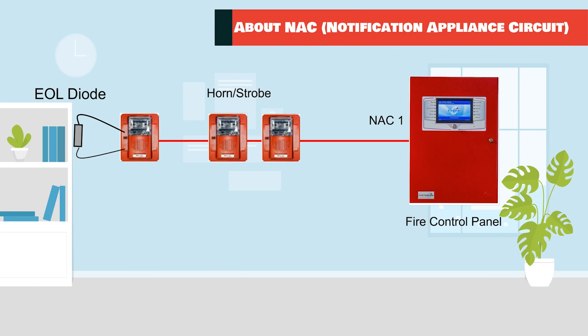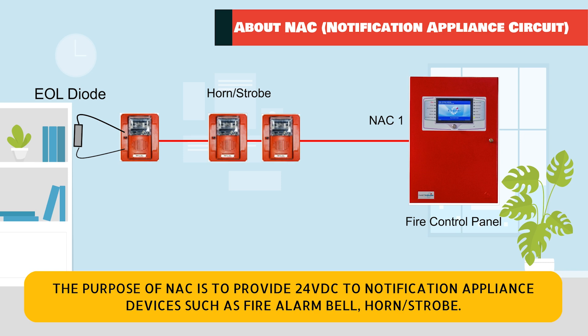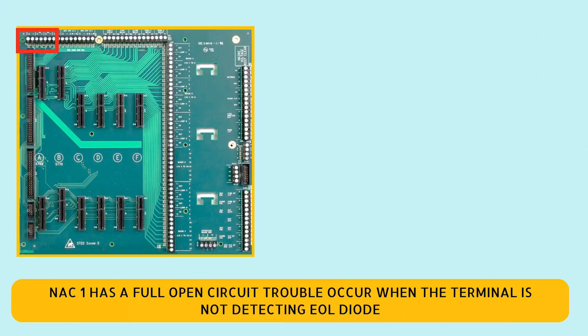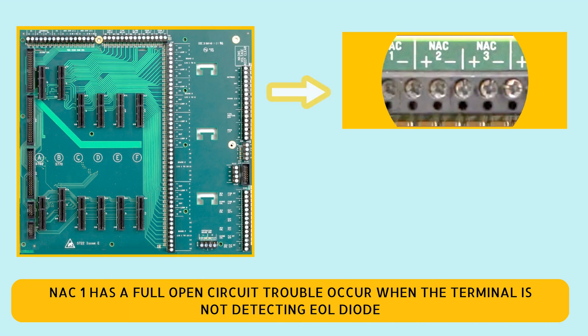The purpose of NAC is to provide 24VDC to notification appliance devices such as fire alarm bell, horn, and strobe. I will use a horn strobe in this demonstration. NAC1 has a full open circuit trouble, which occurs when the terminal is not detecting the EOL diode.